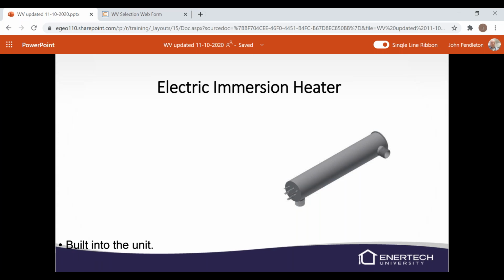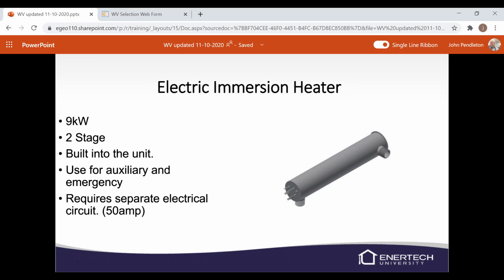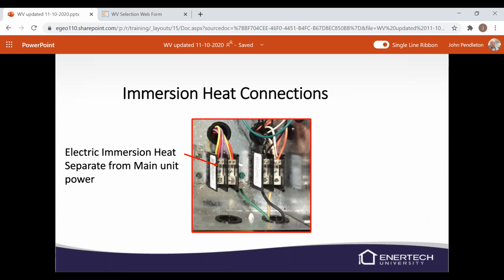Electric immersion heater, again, it's built into the unit. It's 9 kilowatt, 2-stage. You could leave it disconnected. There's ways to set it up in the controller to have a delay on it. You can turn it all the way off, but it will require a separate 50 amp circuit. And there is basically the power block for the heater if you're going to run your power in from the breaker panel, and there will be a sticker located on it.